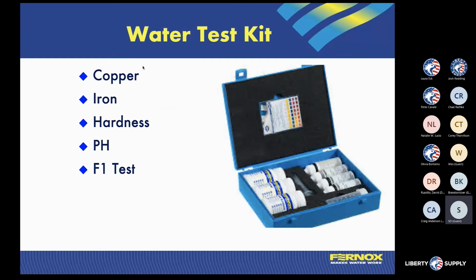So water test kits, we sell a bunch of different water test kits. So this is something you can do for field testing, something that is a purchasable item through Liberty Supply. So you can test out your iron levels, your copper, your hardness, your pH, and also make sure that the F1 or our inhibitor is at the proper level. So this is something we sell a little tube that you fill up with some water, and then you could be able to do your system test before and after. So if you're doing maintenance on a system that's already been inhibited, you could use that same testing function to pull a little sample out, test to make sure that the F1 or the inhibitor levels is at the proper level. You also could do some tests on newer systems or existing systems to make sure that your pH and your hardness are in check as far as that's concerned.